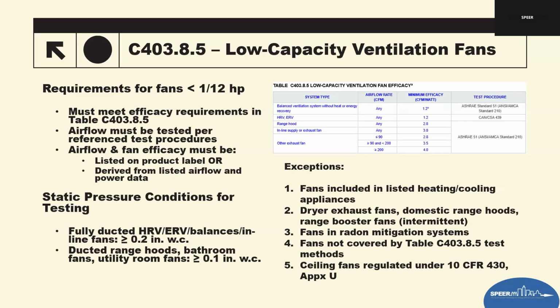So small fans may not be a major energy use individually, but when you have multiples being used in multiple units and then you multiply that times what it is in the commercial building, that adds up. So ensuring that they meet minimum airflow and efficacy requirements improves both energy efficiency and indoor air quality. So plan review tip, verify product submittals show airflow and wattage, or you'll have to look up in the manufacturer's paperwork. Confirm fan types fall under the required test method. Check static pressure readings or ratings used for testing. So that would be by a third-party commissioning. Identify whether an exception is being used, and they're taking one of the 5 exceptions.